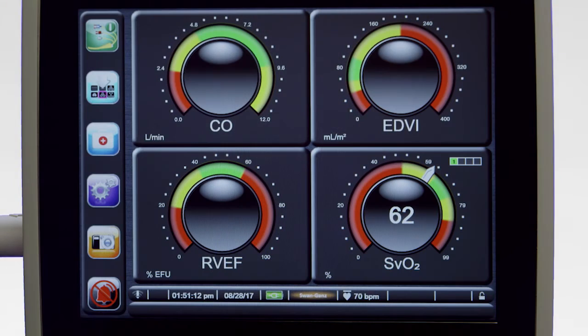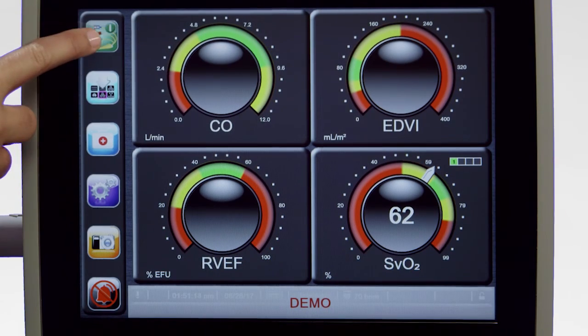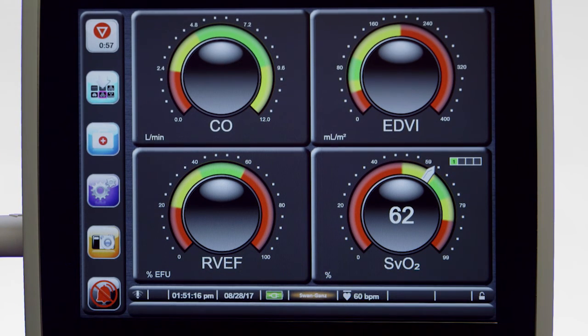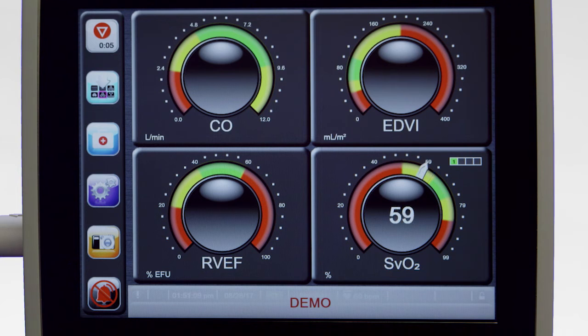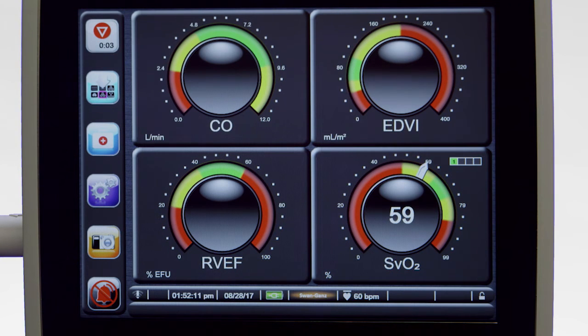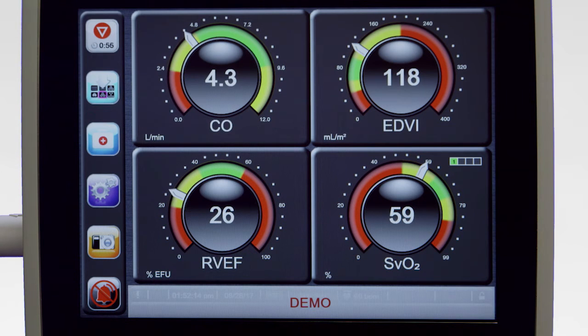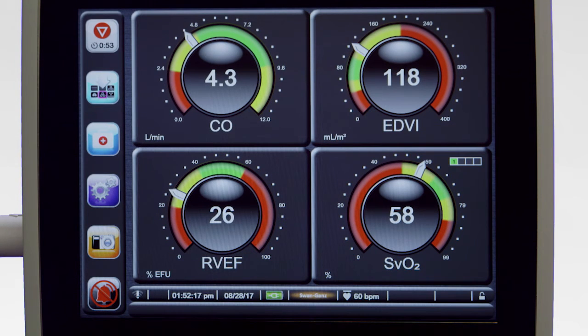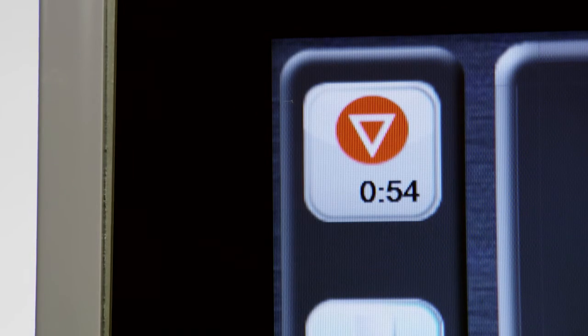To begin CCO monitoring, touch the Start-Stop icon in the menu bar. After approximately 3 to 6 minutes, once sufficient data has been obtained, a cardiac output value will appear in the parameter globe. The CO value displayed on the screen updates approximately every 60 seconds to 3 minutes. The countdown timer in the Start-Stop icon of the menu bar will display the time remaining until the next CO measurement is performed.